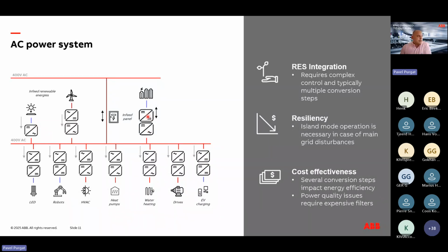We need a DC-DC conversion to adjust the voltages for the battery, for example. And then we have a DC bus, and then we need to make an AC. And this is sometimes more complicated than it looks because we need to synchronize on the grid, we need to adhere to the grid codes, and so on. So especially as we are getting to the grid edge, even though these systems are very resilient, very robust, we end up with many conversion stages and relatively complex system design.